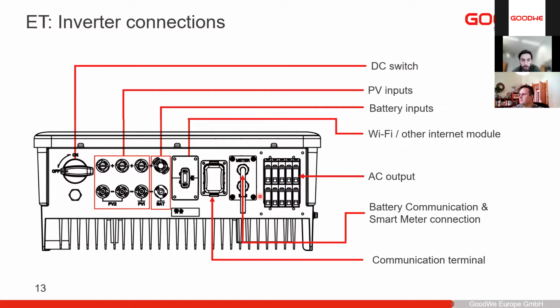Moreover, make sure that you always have the CTs connected as close as possible to the grid connection point, because that's where the CTs are, that's where the inverter will limit power. In case you want to have any power export limitation, they need to be just before the grid connection point, and also to measure the load consumption, they need to be after all the loads and just before the grid connection point. So make sure that you're always connected there.